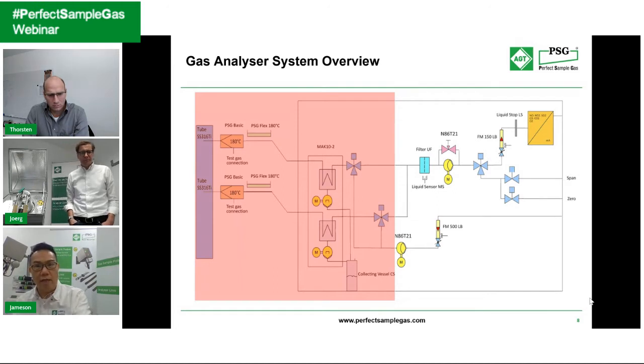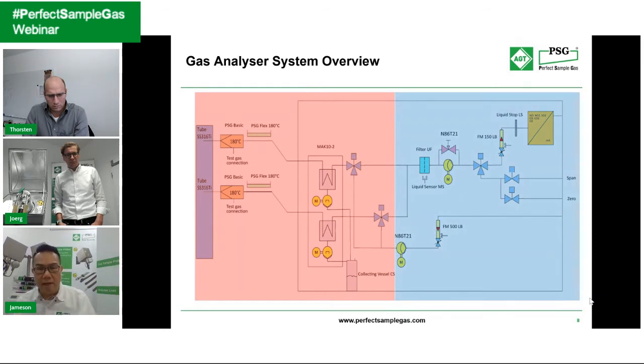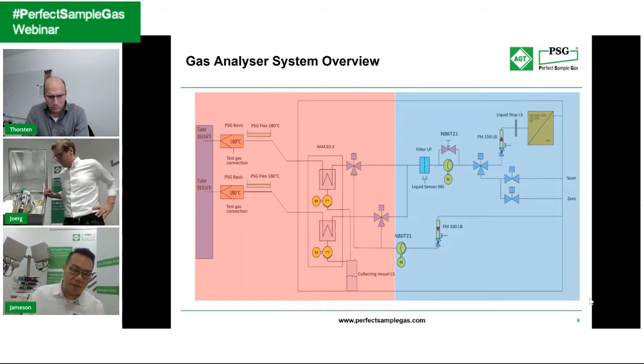Another area: we know that there is a pump. The pump is siphoning the negative-pressure sample and delivering it to the gas analyzer, so make sure that you minimize the back pressure, all right? Never put a pressure regulator, and never oversize a sample pump so that you are not able to have a good bypass, creating a back pressure. Once there is enough back pressure from the pump outlet to the gas analyzer to change the dew point, that is where all the maintenance you have to address down the road comes from. So this slide tells you, I repeat, that the red color means you must stay above the acid dew point, and the blue color means making sure you do not have enough back pressure to change the acid dew point.